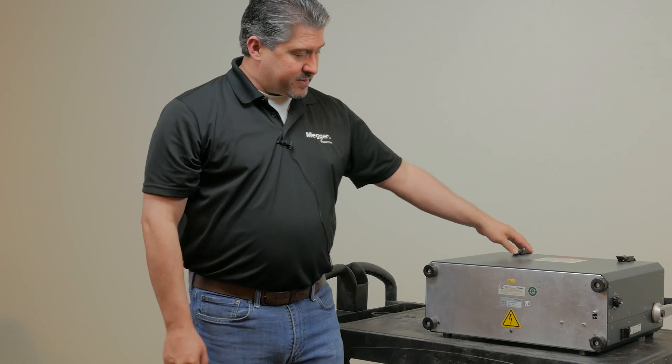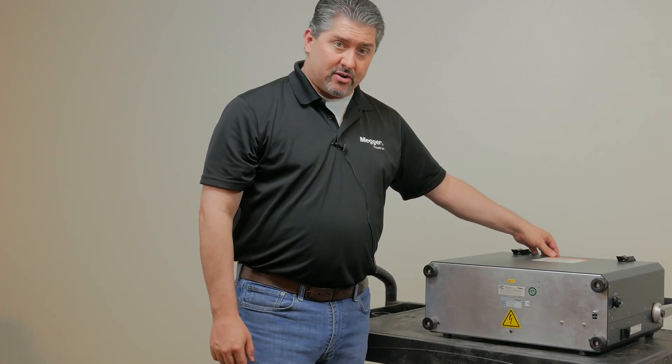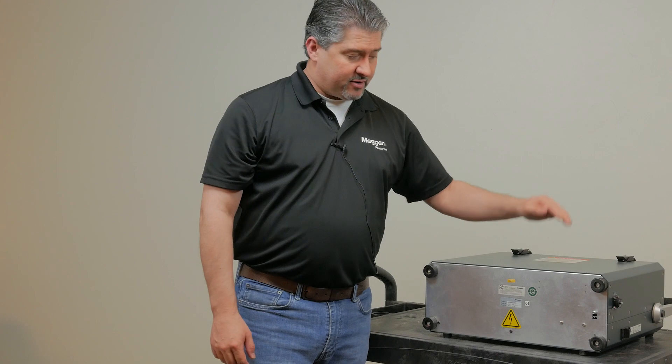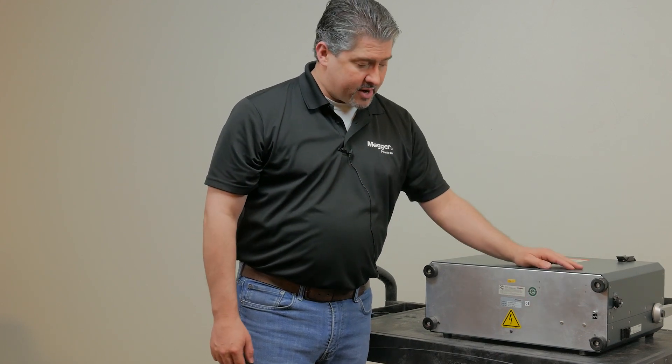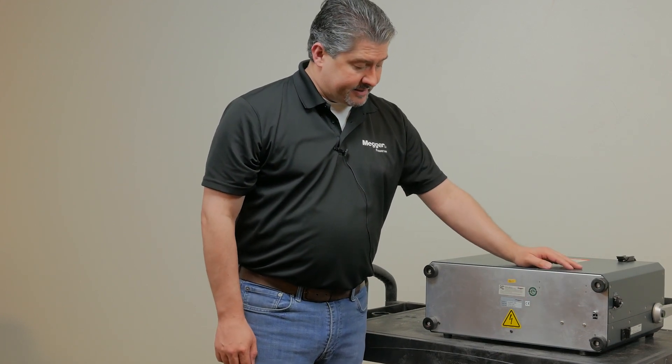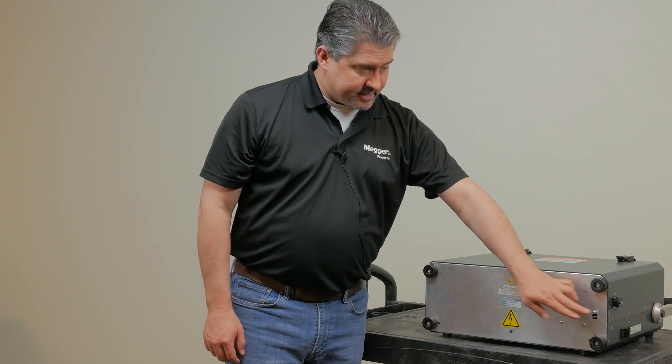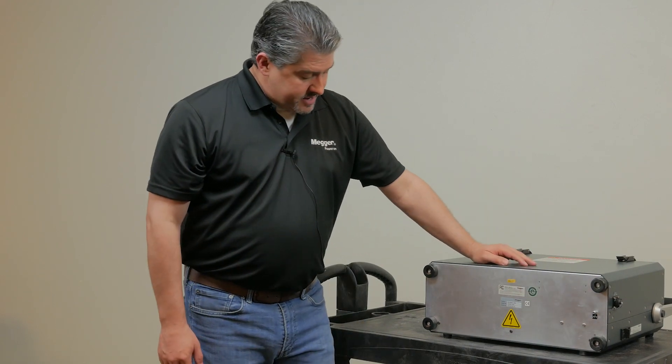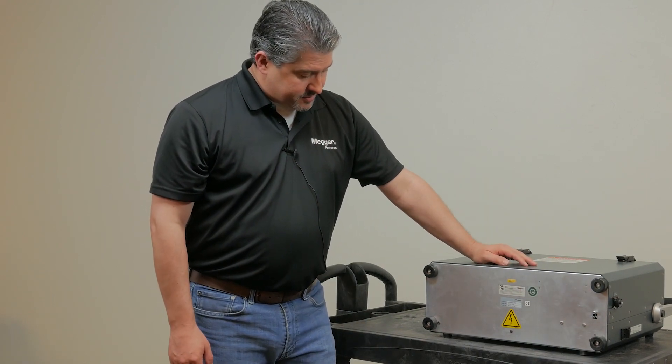And that's because we have the open ground interlock. If you override that interlock, you want to ensure that the chassis is properly grounded before you override it. So you just connect a lead there to earth ground and you'll be safe and good to proceed with testing.